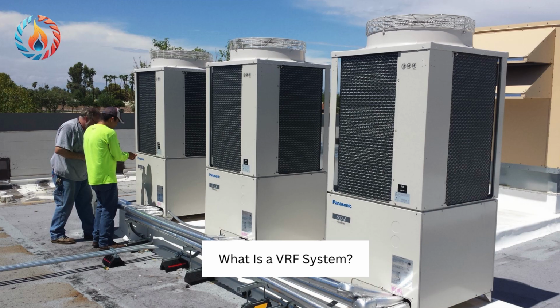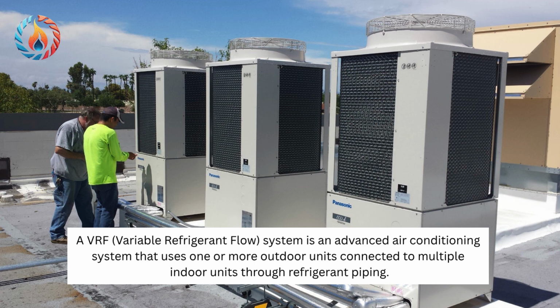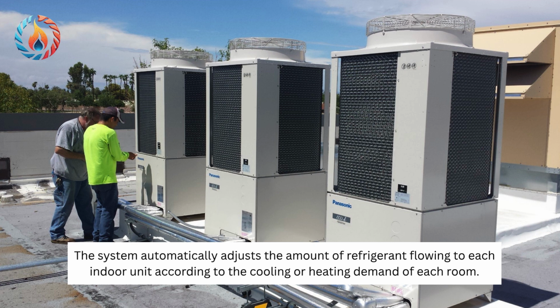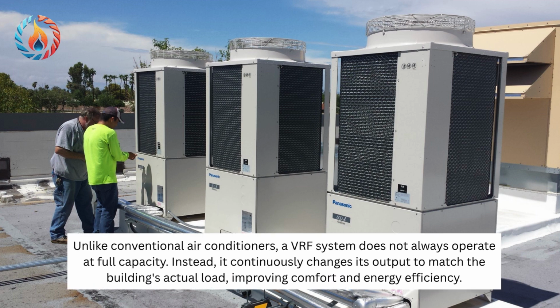What is a VRF system? A VRF, Variable Refrigerant Flow system, is an advanced air conditioning system that uses one or more outdoor units connected to multiple indoor units through refrigerant piping. The system automatically adjusts the amount of refrigerant flowing to each indoor unit according to the cooling or heating demand of each room. Unlike conventional air conditioners, a VRF system does not always operate at full capacity. Instead, it continuously changes its output to match the building's actual load, improving comfort and energy efficiency.